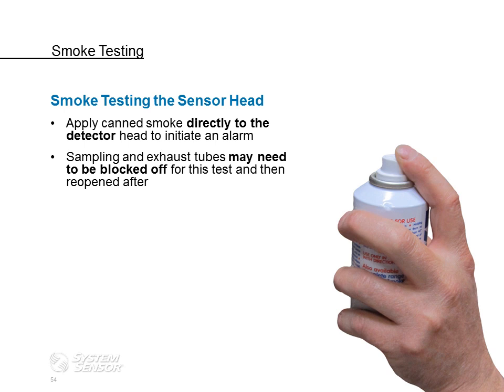Smoke testing at the sensor head: apply canned smoke directly to the detector head to initiate an alarm. Sampling and exhaust tubes may need to be blocked off for this test and then reopened afterwards, depending on where it's at. That's one way to do it. There is also another way to do it, where you basically make a penetration in the ductwork upstream, spray the smoke into the ductwork, and let it be drawn through the sampling tube. That's the second way to do it.